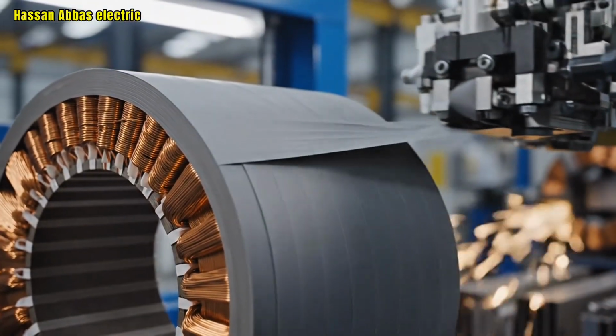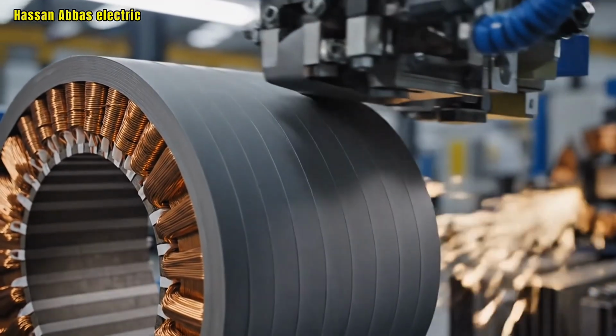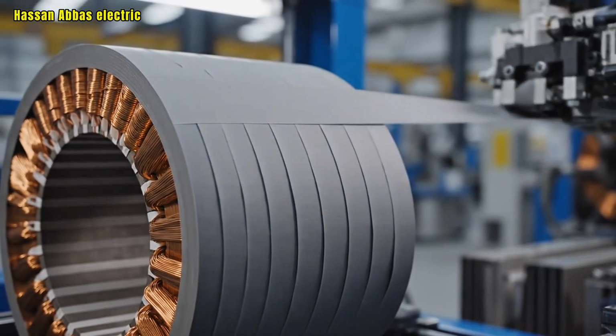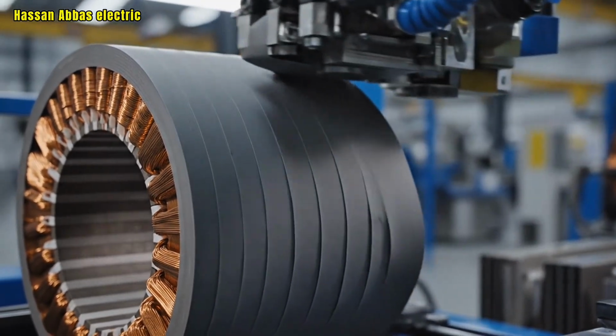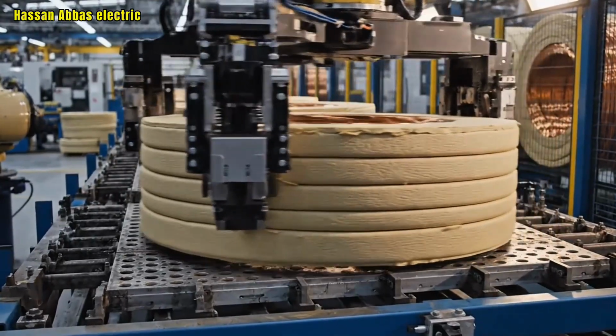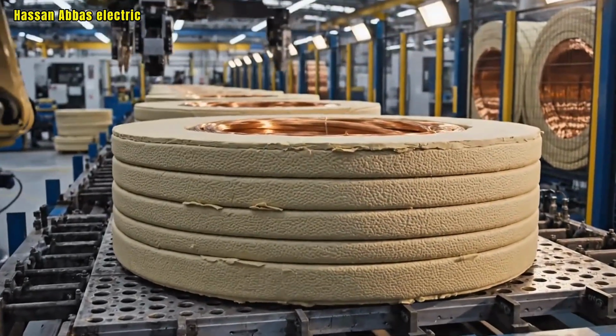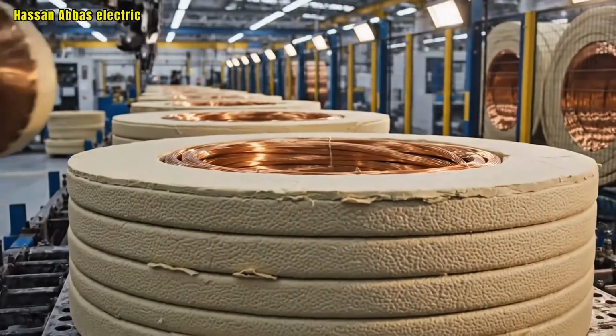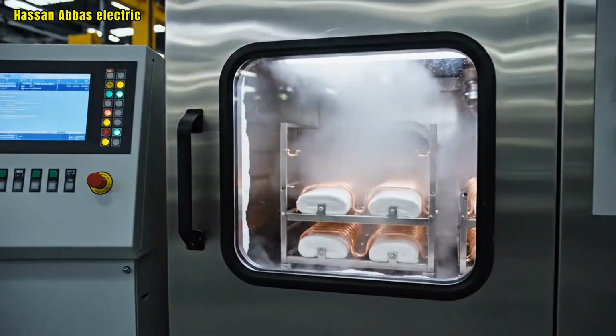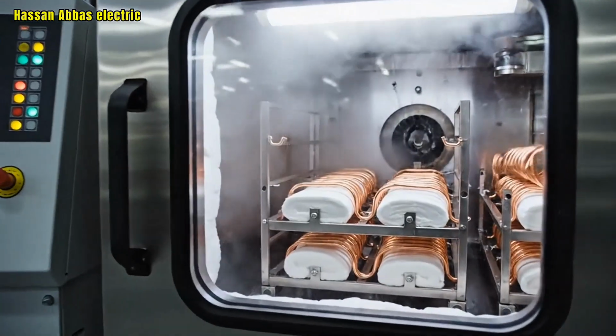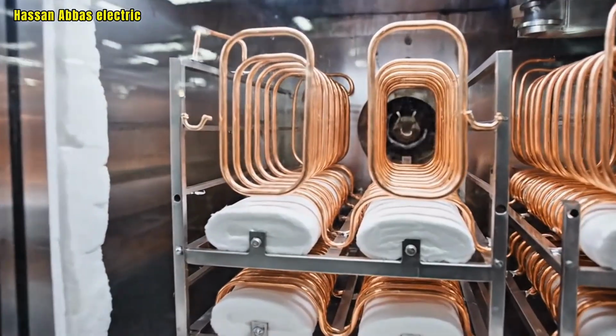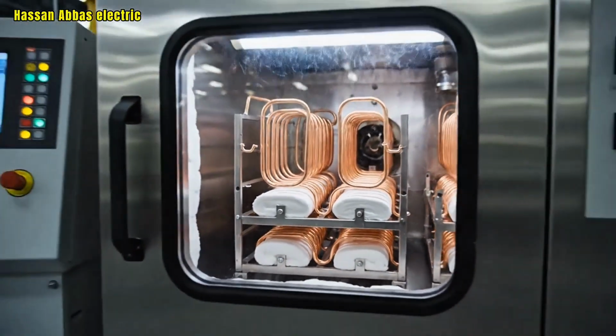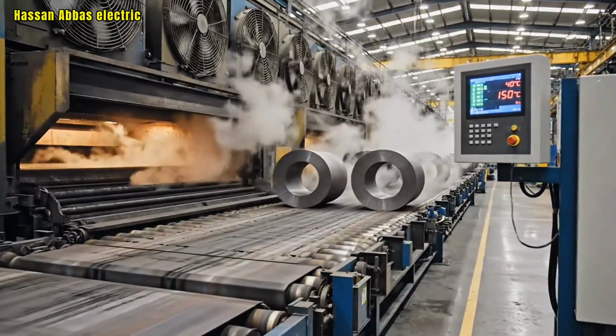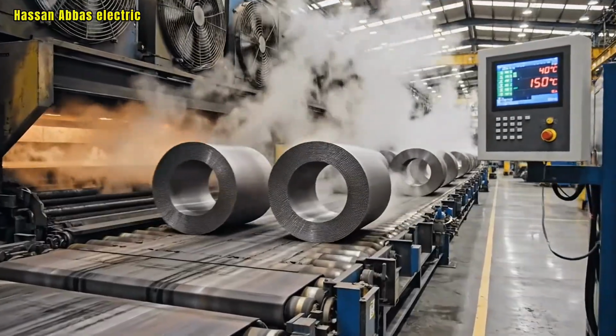Insulating tape is applied to fully protect the transformer coils. Coils are prepared for drying to remove moisture before assembly. Coils undergo vacuum drying to ensure insulation is moisture-free. Dried coils are cooled to room temperature before final assembly.